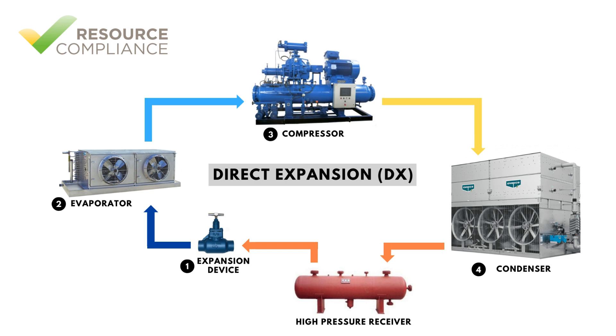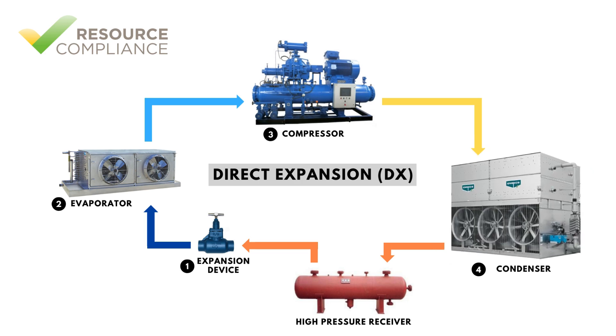From the compressor, the high-pressure, high-temperature vapor is piped to a condenser, which is a heat exchanger whose purpose is to reject the heat gained in the evaporator and compressor to a place where the heat can do no harm.